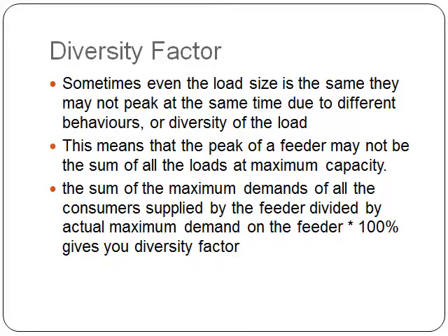Diversity factor. Sometimes even when the load size is the same, they may not peak at the same time due to different behaviors, or diversity, of the load. This means that the peak of a feeder may not be the sum of all the loads at maximum capacity. The sum of the maximum demands of all the consumers supplied by the feeder divided by the actual maximum demand on the feeder times 100% gives you what is called the diversity factor.